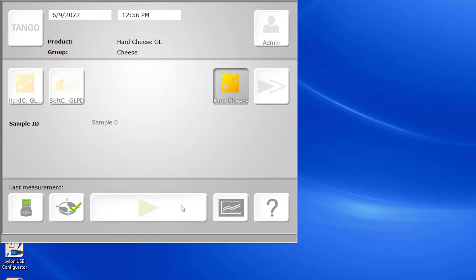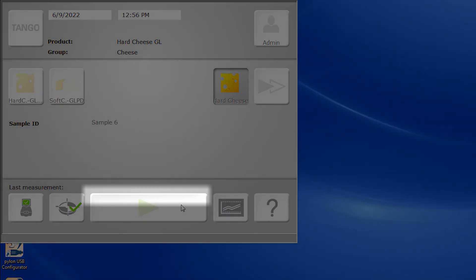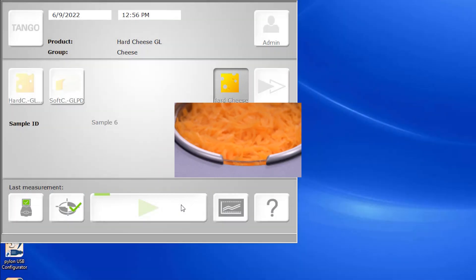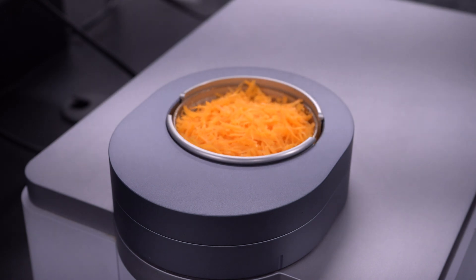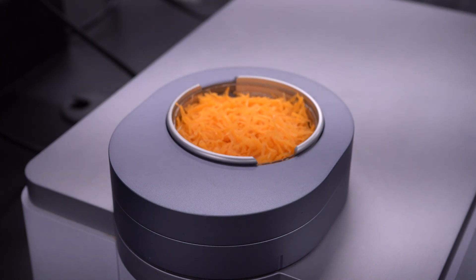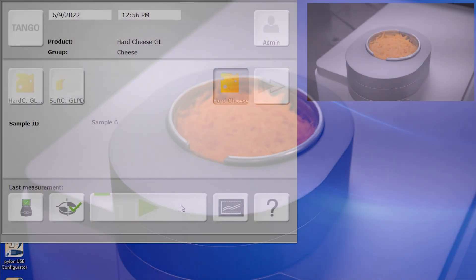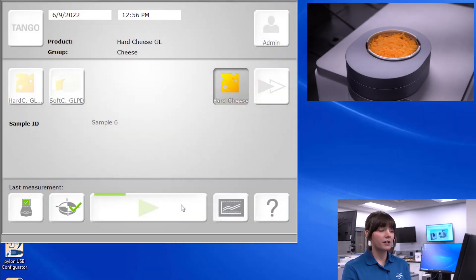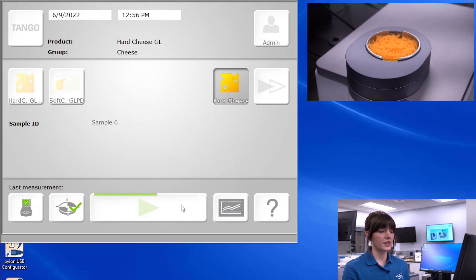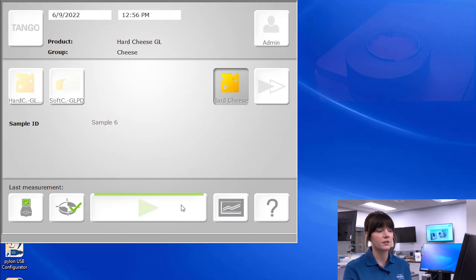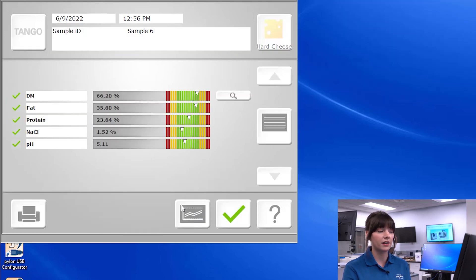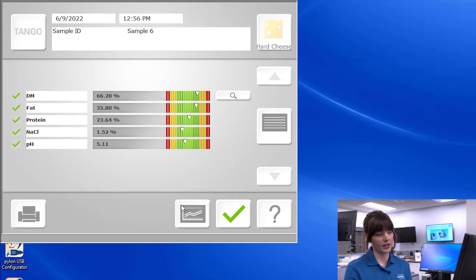While the measurement is being taken, we can visualize this progress with the green progress bar. We can also see the cup rotating around as a multitude of scans are being taken. When we measure a sample, our software compares the measurement, or the average of these multiple scans, to the background and generates a spectral file in which all that information is taken into consideration.